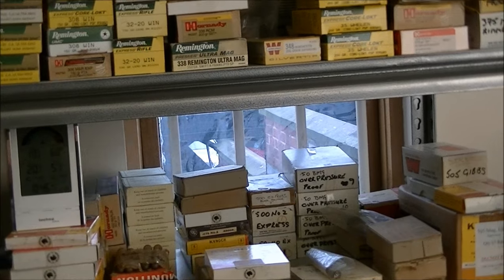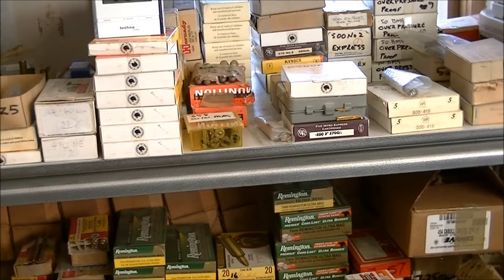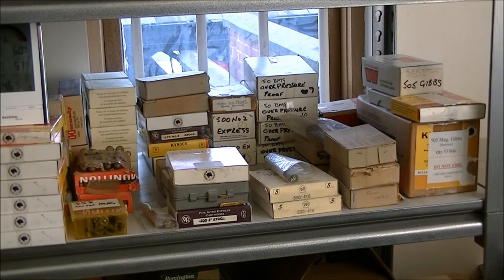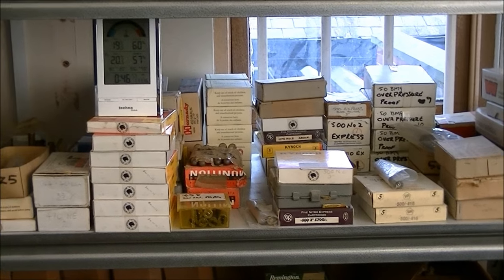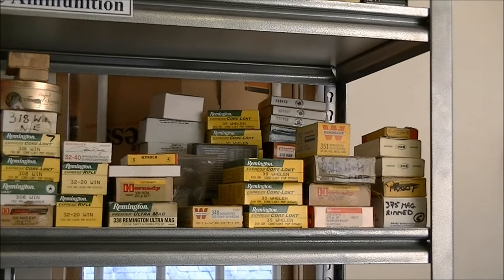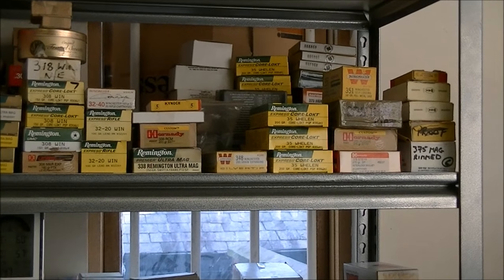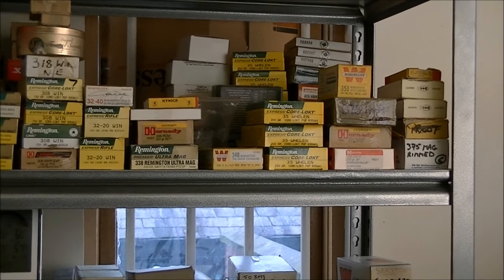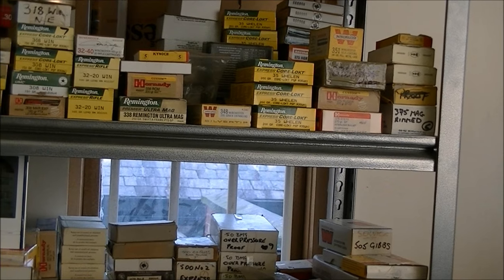It's all calibrated to UKAS traceable standards - the ISO 17025 standard. Our governing body, the CIP, wants all participating laboratories to have this 17025 standard. I think there's only one or two others within Europe that have got this 17025 standard. There are a number of other proof houses - there are 15 or so including Italy, Belgium, France, Russia - and we are intending on achieving the required standard. This is some of the equipment we need to have to be able to do so.